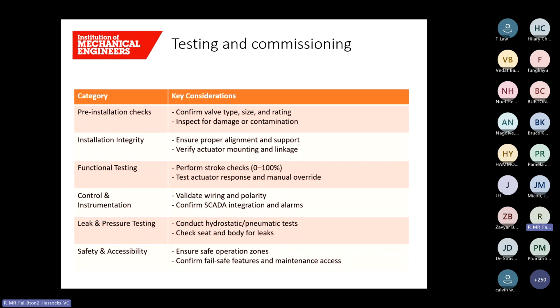Control and instrumentation: validate wiring and polarity. Confirm SCADA integration and alarms. Leak and pressure testing: conduct hydrostatic and pneumatic tests, check seat and body for leaks. Safety and accessibility: ensure safe operation zones, confirm fail-safe features and maintenance access.